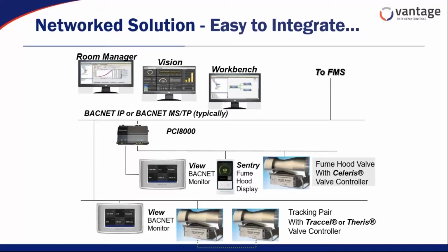Now, if we look on the system above that says fume hood valve with Celeris valve controller, those Celeris valve controllers use a proprietary network architecture, and that's to communicate between the fume hood valves, the supply valves, and the general exhaust valves, as well as the fume hood display that's controlling what's going on in those wet chemistry fume hoods. So in that particular environment, we need a device to convert the data from our proprietary network up to the building automation system. In that scenario, we use what we call a PCI 8000. And that's a Tridium Niagara based product.